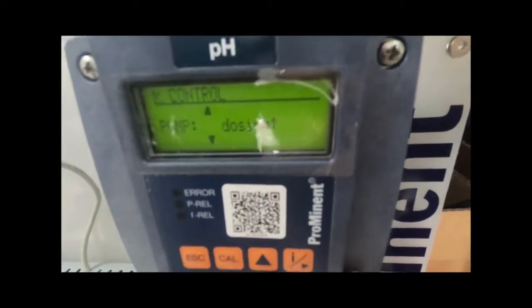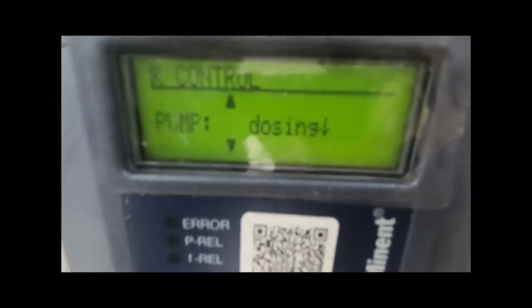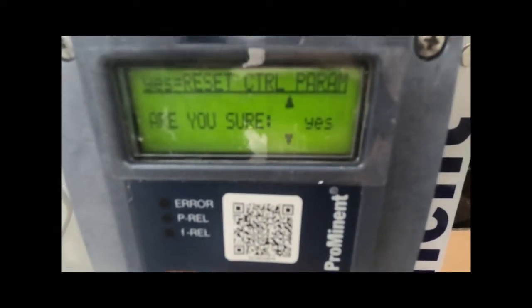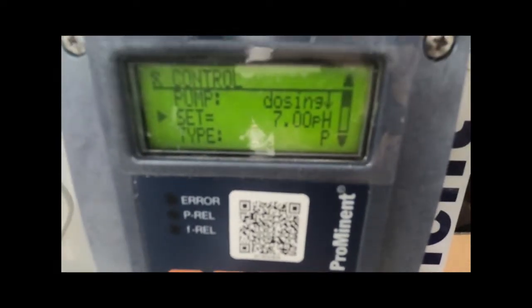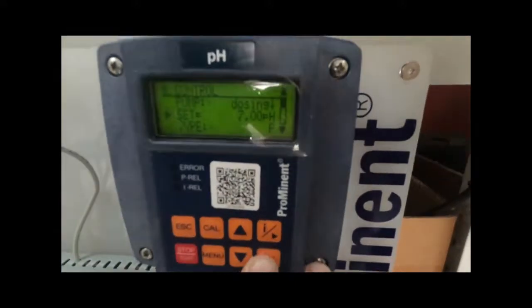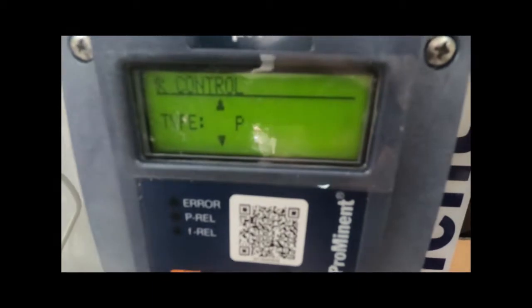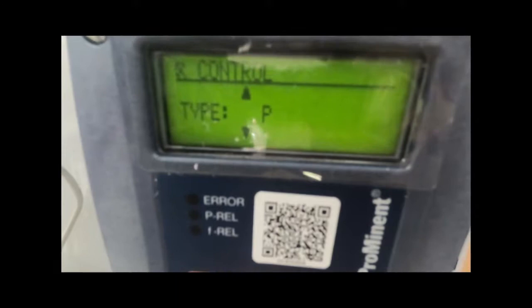For this panel, we are going to put it down because we are going to dose acid. Then we'll say yes. If we need the pH more than 7, we have the curves here for the side. We can go for 6 or 8, as much as we want. So for this one we are going for 7. Then we'll press OK. The type of the dosing, if you need it on proportion or PID or manual. For this system we are going for P for proportion dosing.